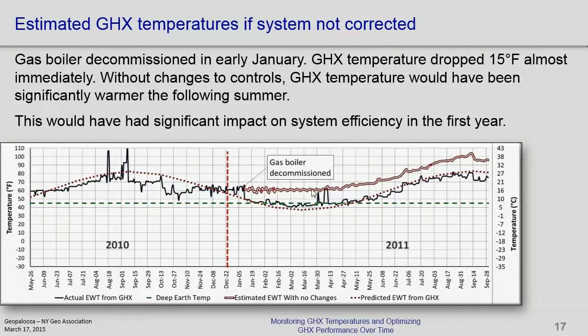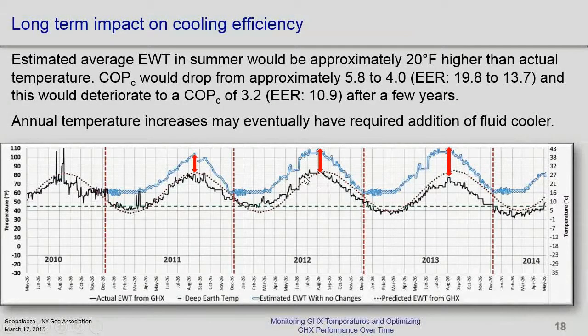And then as soon as it dropped again, it would start climbing again, or the temperature would climb up. End of August, be up pretty high. So here's what was estimated that the temperature would have been if we hadn't caught it. So basically, it flattened out here, flattened out again, and each year probably get a little bit higher. And eventually, if not this year, eventually they would have to put a cooling tower in there to prevent the ground loop from overheating all the time. And that's no fault of the system. That's simply the way the system was being operated or controlled.